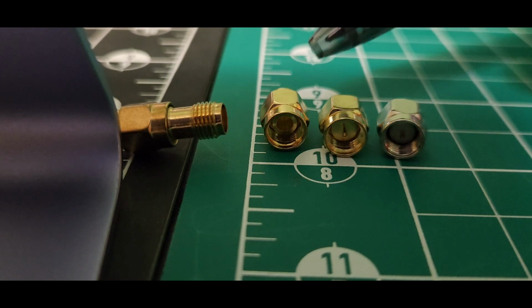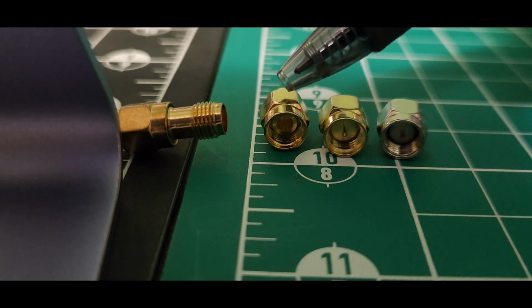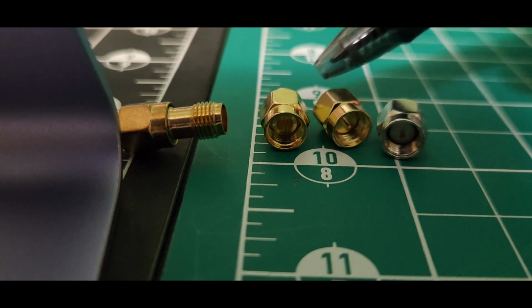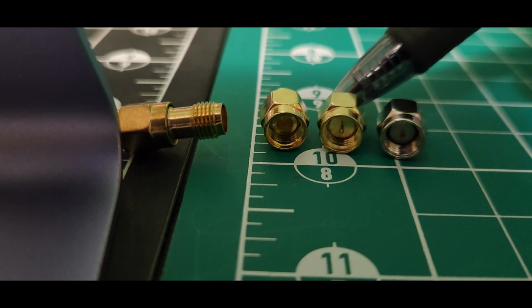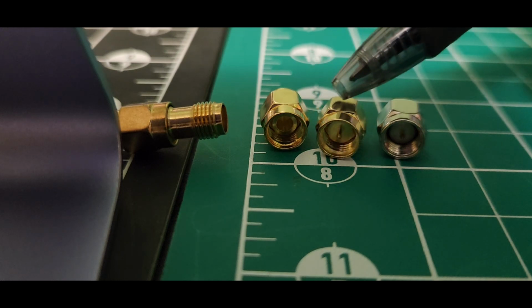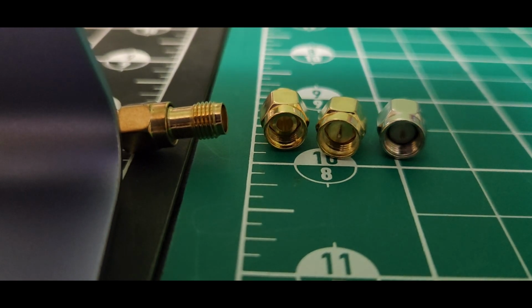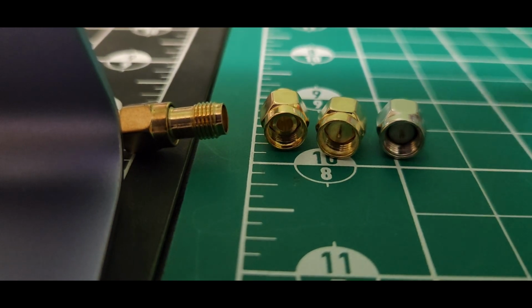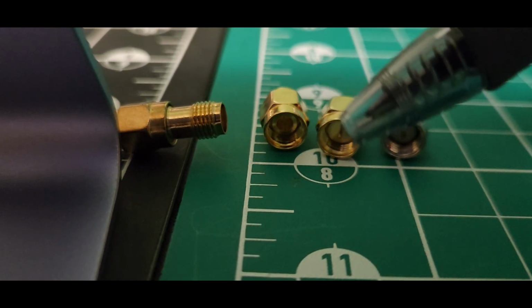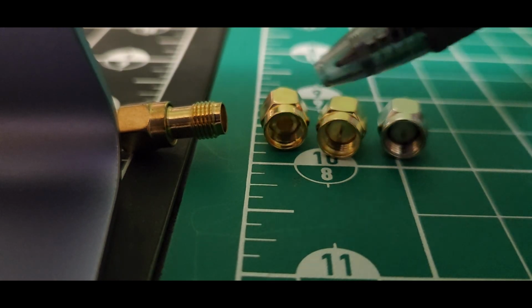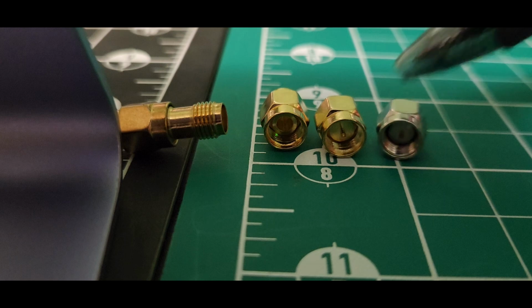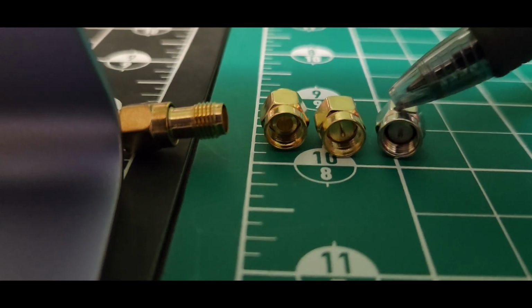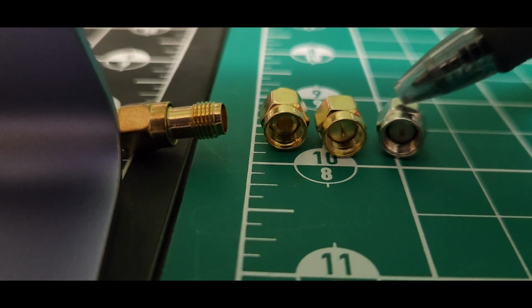The first calibration slug is open circuit. The next one here is closed, or we click calibrate, we have short. This is the shorted condition. So we have open, short, and load, which is a 50 ohm load, simulating what we find in most proper antenna systems.